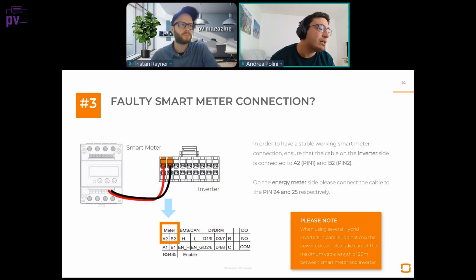Also, another way you can see that there is something wrong with the energy meter is if you look at the production data on iSolar Cloud, you will see that the house load data has a very similar shape as the PV production data. So when the load curve, the yellow one, looks quite similar to the PV production curve, the orange one, it means that the inverter is not getting any usable information from the meter, and this is why it's conflicting in the calculation of the house load, essentially. And this is also another way you can easily find that there is some issue in the communication of the smart meter.